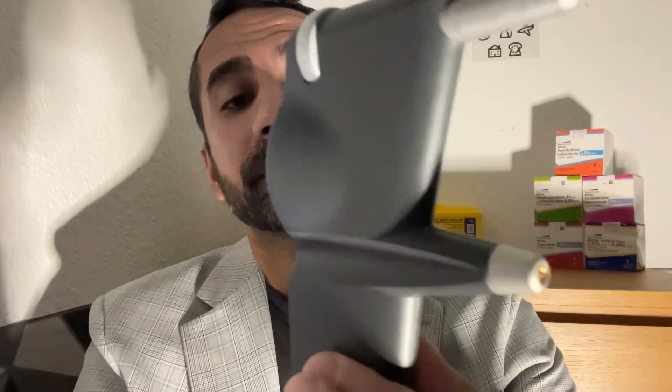The head support keeps the device nice and steady when performing the test. We load our tonometer probe, turn the device on — it gives us a little beep — and it asks us to load the tonometer probe. We load it, press the button, it magnetises and stays nicely attached. We then perform tonometry with the Icare, taking six readings per eye, and it takes the average of all the readings.